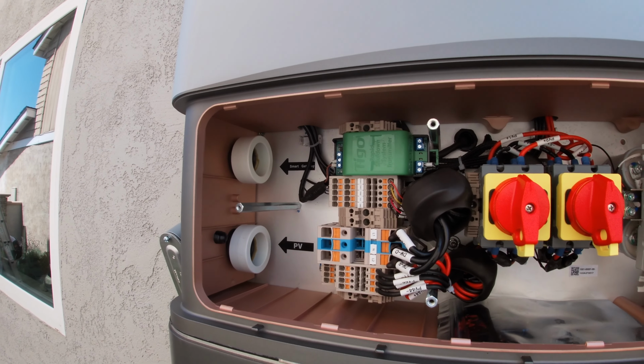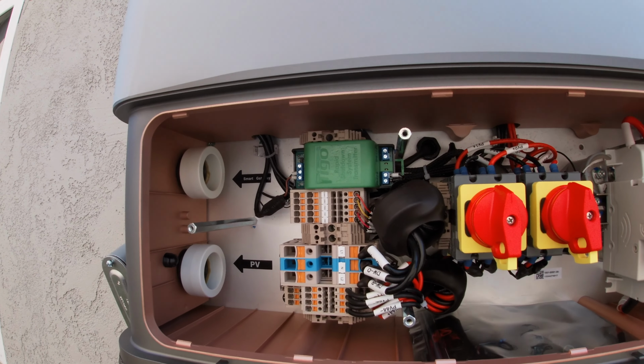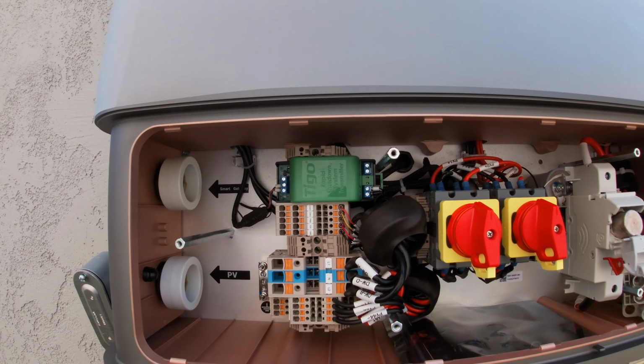So if you have a nice big ground mount and wanted to do DC coupling, you have 4 inputs, MPPTs, for PV strings. So your DC modules go straight to the inverter for DC to DC charging, great for round trip efficiency, though this has a phenomenal AC round trip efficiency too. But that would mean you now have a port for EV charging as well as that backup generator. So you do make a sacrifice if you have an AC coupled solution, but as a whole product, you have a lot of options if you're going with a brand new system.